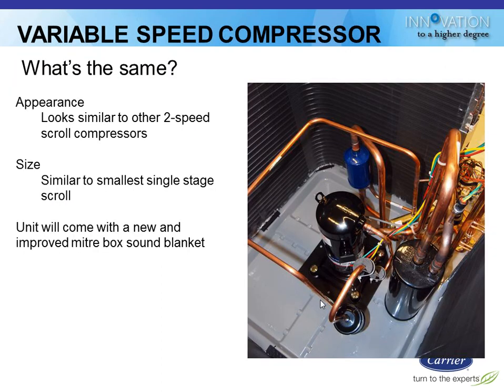There's what it looks like from the top view with all the components on the inside. So the black unit obviously in the middle is the compressor. Normally he would have 2 sound blankets on top of him. That blue guy is the muffler. The black guy on the right side is the charge compensator. Down in the middle, the brass colored one is the reversing valve. So that guy switches it between heating and cooling mode.